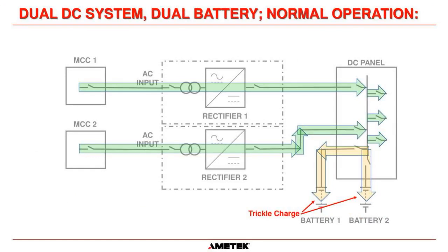So the power flow for a parallel system is, as you can see here, the green arrows. Both chargers are in parallel, so they will go onto the DC bus at this point here, and they will feed the load circuits, and they will also keep the batteries trickle charged. And this brings up one of the most contentious points of paralleling DC systems: should they load share? Now, I might go into this later on in the presentation. It's been a while since I did this one, but I'll go over this subject right now. In my opinion, and remember, it's only my opinion, there is absolutely no reason whatsoever for two chargers in parallel in DC systems to share the load. Absolutely none whatsoever. Okay, let me explain this.